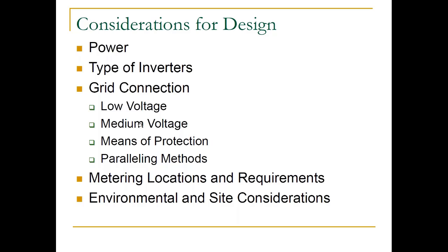How are we going to connect to the grid? Is it going to be a DC connection to a paralleling board at DC? Is it low voltage AC paralleling boards? What's our means of protection going to be? Are we going to have fuse conductors, fuse switches? We're going to have circuit breakers. Are there protective relays involved on that main breaker or on the riser pole up to the utility connection? And what are the customers' metering requirements? What are the utility metering requirements? And what different site considerations are there for the installation?